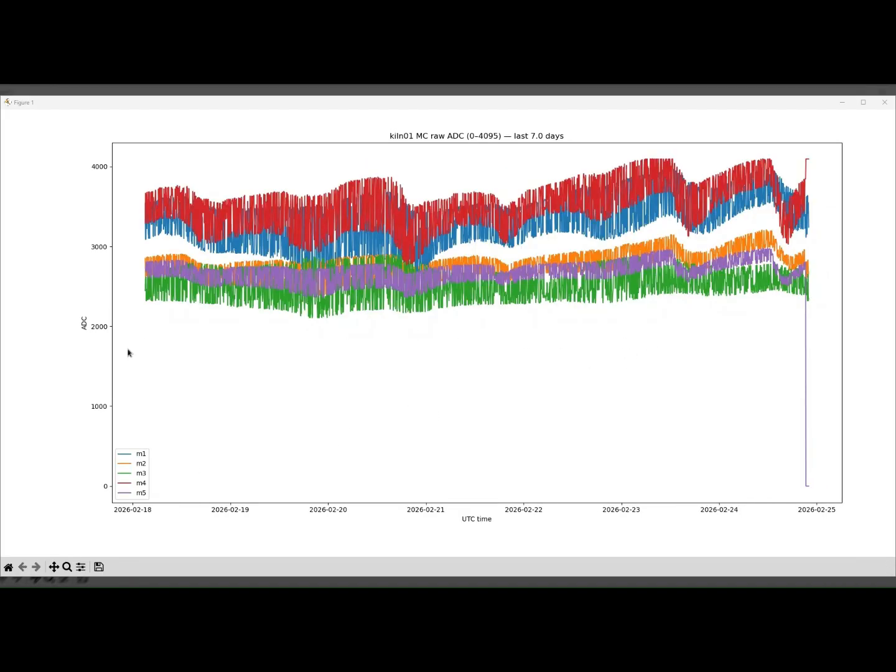All right, I have pulled 7 days of data. You can see where we made the changes. The purple one again was shorted, and that was the longer cable. The red one was open, and that one is closer to AC, and it's one of the biggest noisy ones. So are we dealing with AC getting onto our wire? Maybe a shielded wire might help.